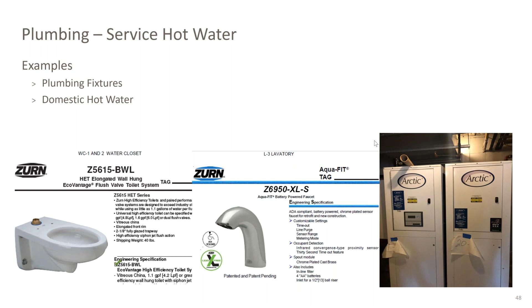One of the concerns, certainly in the Mid-Atlantic, is that we reject more heat into the ground than we take out of the ground. So one of the ways to combat that argument is to, where we do need heat, domestic hot water, take that heat out of that geothermal loop. So this is always taking heat out of that loop, even summer and winter.